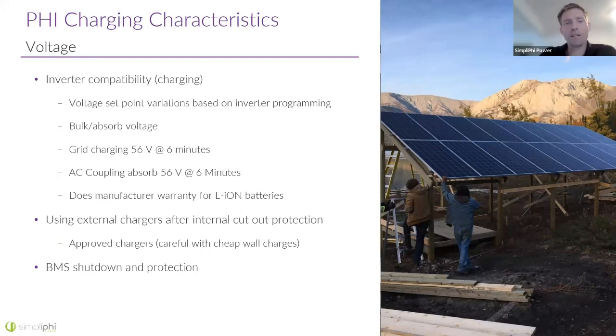Now, sometimes the absorb setting, you won't be able to set a time limit for that. What do we do for that, Daniel? When you can't set the absorb time to 6 minutes, what can you do? We can adjust it to where the end amps, if it's 2% of the battery bank's amp hour capacity, would be the limit, and we would then stop that charge rate. Great, thank you. Exactly, right? So if you can't set the time on your absorb cycle, what you can do is just set the end amps, and that's the rate.